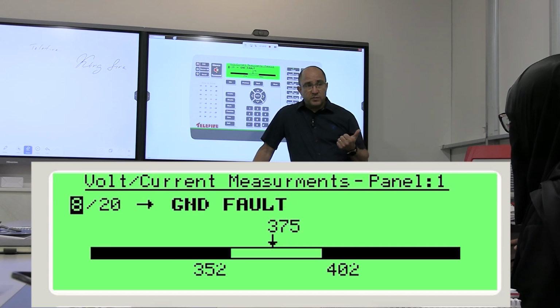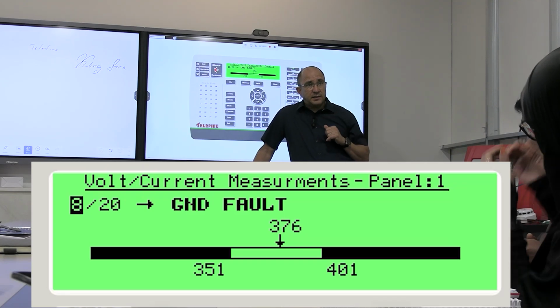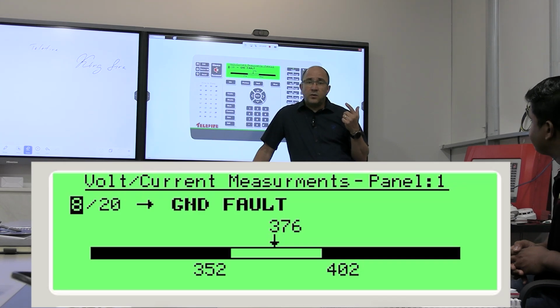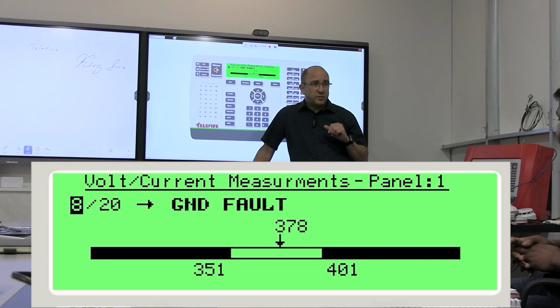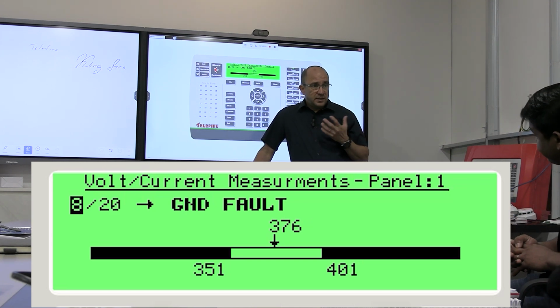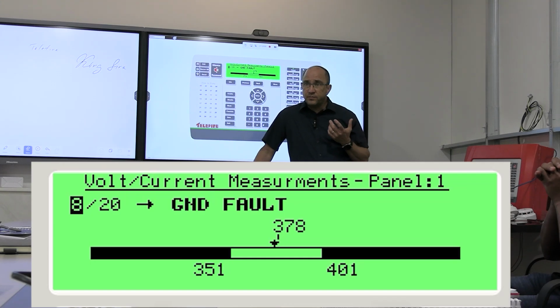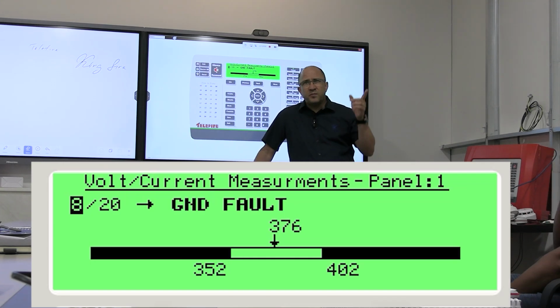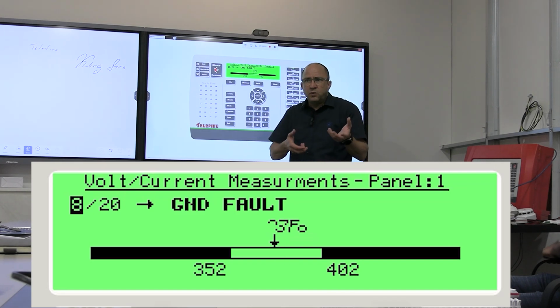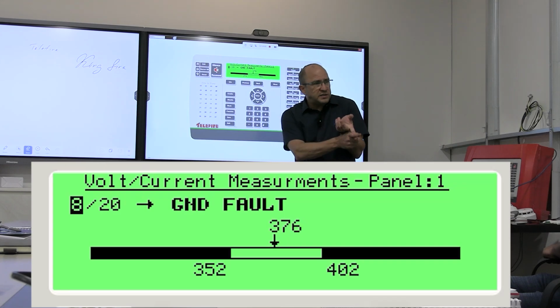Did you have water problems here? From the air conditioner? From the last rain that we had? Did another work guy come here? Electrician? Somebody that worked on the ceilings? Air conditioner guy? Did any professional come here and do something? If they said yes in the 4th floor, but in that room, but it's got nothing to do, okay, please show me. And then you see, while he was pulling wires, he moved your wire, and your wire is touching the metal.